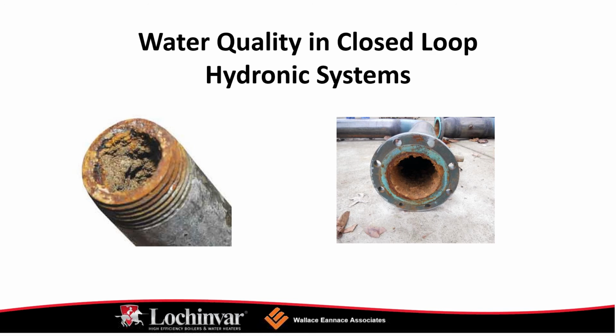Maintenance and service. In general, we want to address reported problems. Inspect the interior, clean and vacuum if necessary. Clean condensate trap. Fill with fresh water. Obviously check for leaks: water, gas, flue, condensate. Verify your flue and air lines are in good condition and sealed nice and tight. Check the water system pressure, system piping and expansion tank.